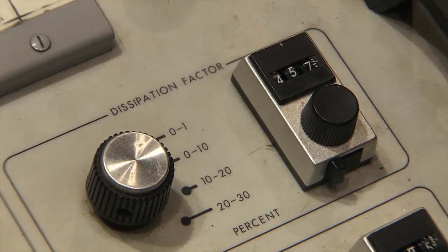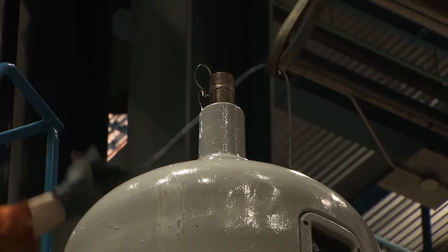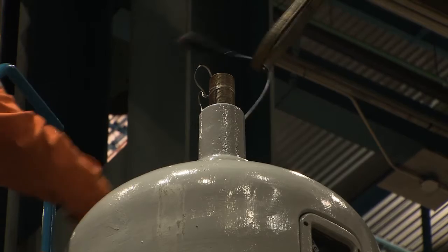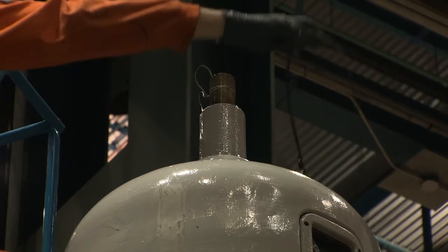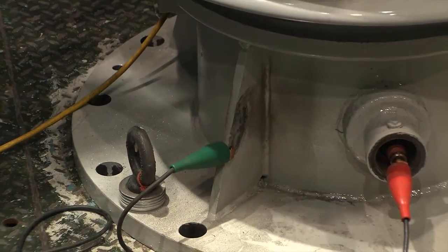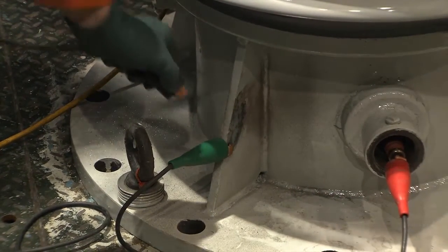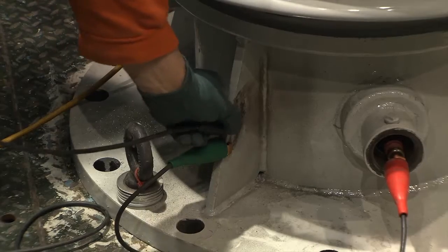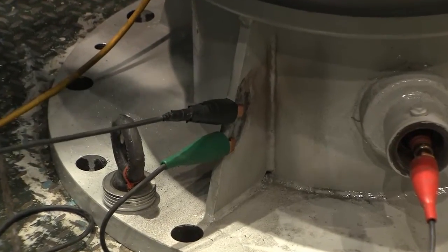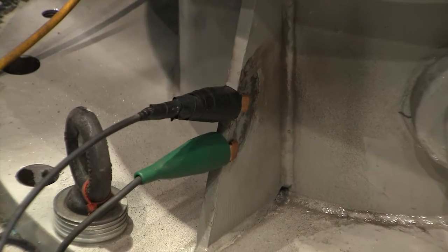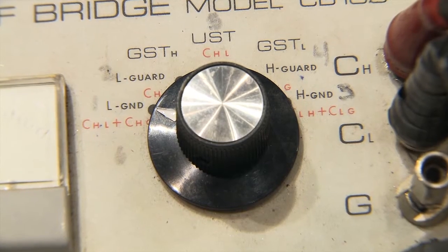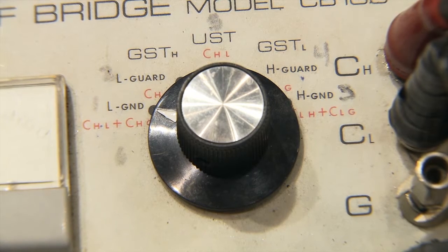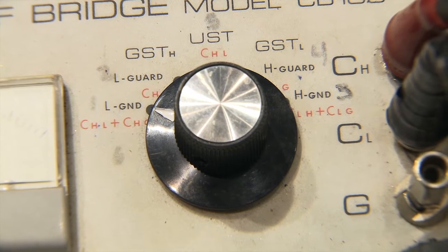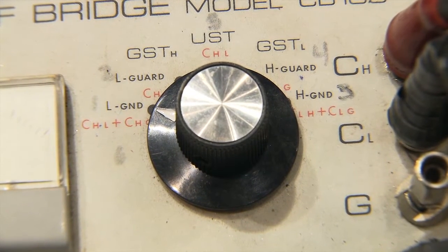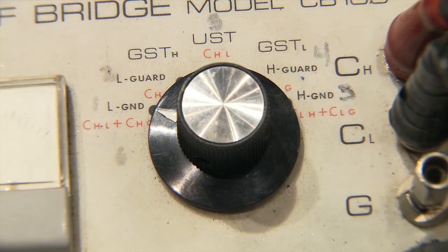We'll call it. To make the connections for the C1 plus C2 test, remove the low voltage lead from the connection at the top of the bushing. Connect the low voltage lead to the bare metal on the flange. On the DF bridge, the selector switch should remain dialed to LGND, that is for the low ground GST test to be performed. UST stands for ungrounded specimen test.